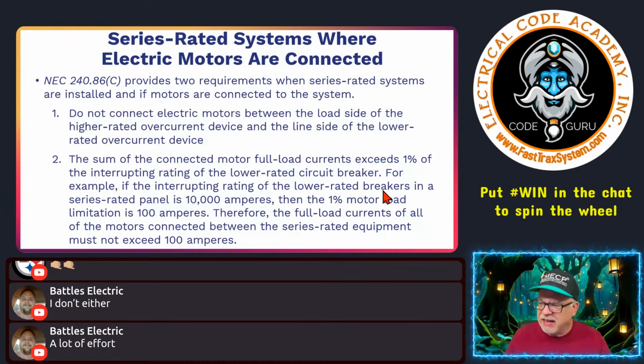Cheaper panel, right? It says, for example, if the interrupting rating of the lower rated breaker in a series rated panel is 10,000, which would be a typical breaker, then the 1% motor load limitation is 100 amps. Therefore, the full load currents of all of the motors connected between the series rated equipment and that motor must not exceed 100 amperes. So we have to make sure that we're looking at the motor that we install, looking at the FLC. Again, these are little nuances. If we're going to do that with the circuit breaker, we have to make sure.